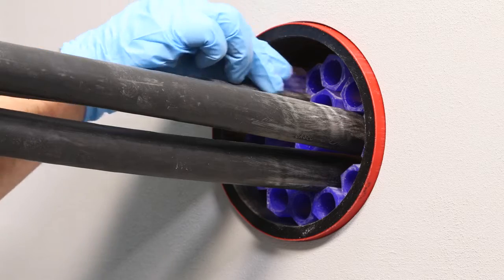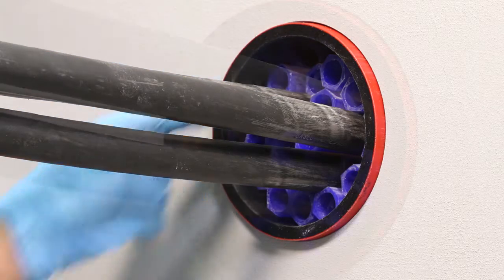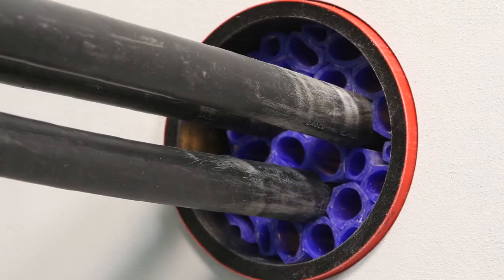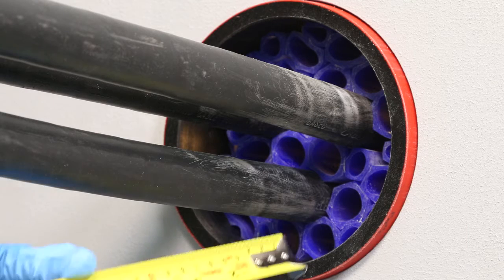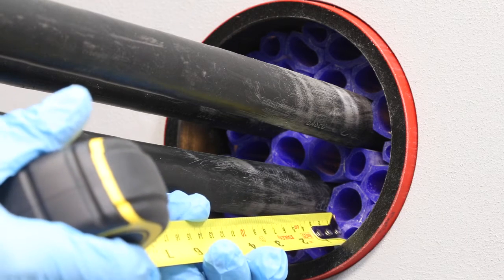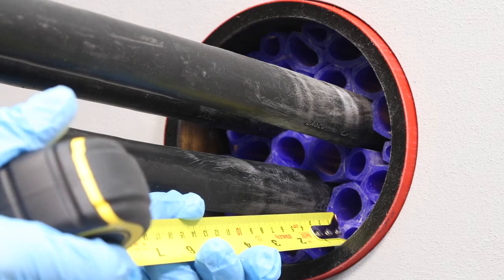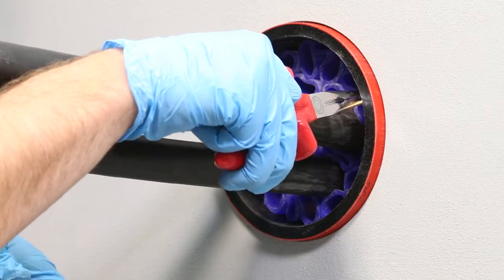All the hexagonal tubes should be inserted into the duct so that there is a clear space of about 20-25mm in front where the MD Plus sealant is to be applied. If the tubes are pushed too far back, you can use long-nosed pliers to pull them forward again.